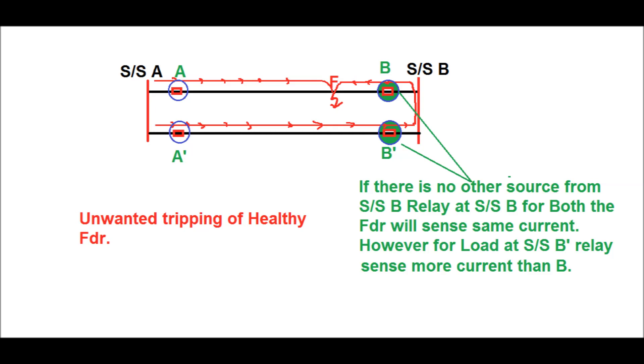Therefore, the load current will add up with the fault current. Therefore, relay at B' will sense more current compared to relay at B. Therefore, it is possible that the B' relay trips before substation B relay.